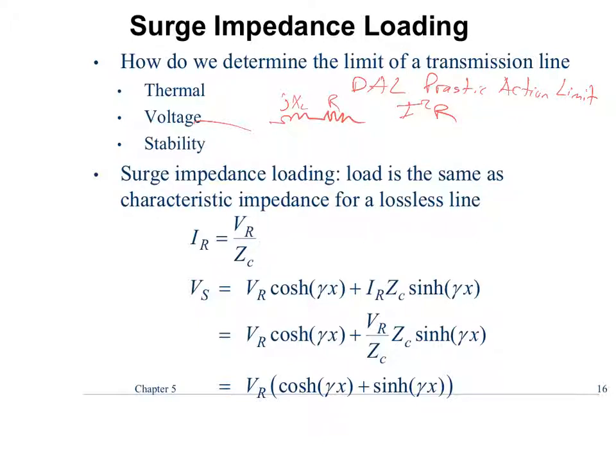Across the line. And as we increase our power demand of the line, right, what happens? The line starts to consume VARs, right? When we consume VARs, we drop voltages across them. And at some point, our voltage limits are exceeded. You can't run one end of a line at, let's say the receiving end has to be at 345 kV. You can't have the sending end at 500 kV, right? It's just not practical. The equipment can't handle that.